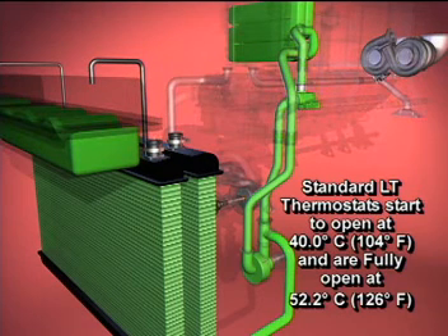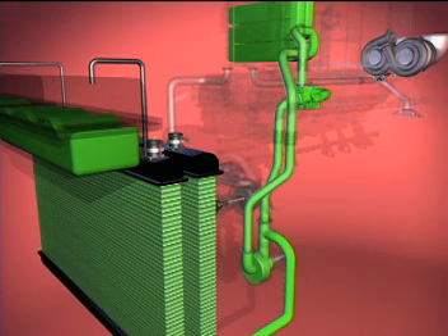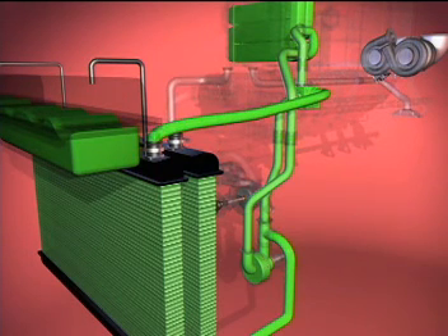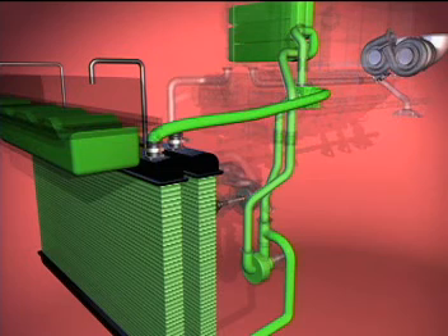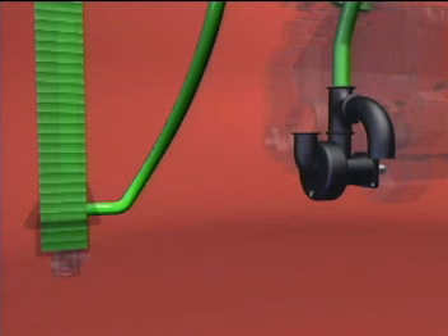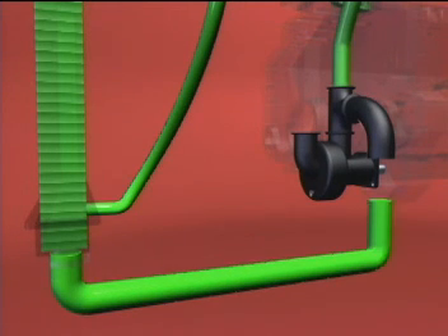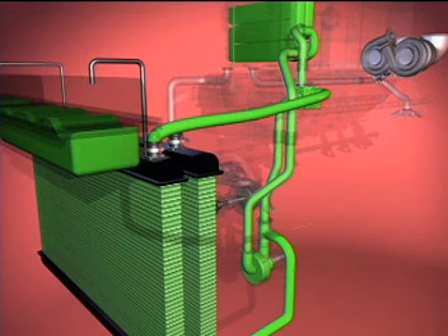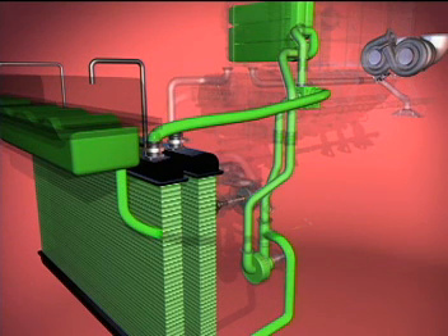When the coolant temperature increases, the thermostat starts to open, restricting the bypass passage in the LTA thermostat housing. When the bypass passage is blocked off, all of the coolant flow is fully directed to the LTA radiator. Coolant returns from the LTA radiator back to the inlet of the LTA water pump to complete the circuit. To ensure a positive pressure head on the LTA water pump, the fill line supplies coolant directly to the inlet.